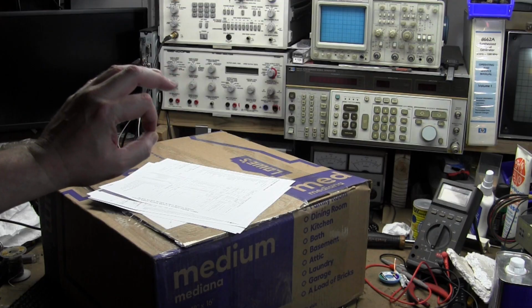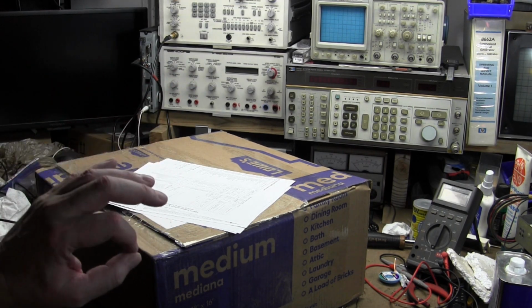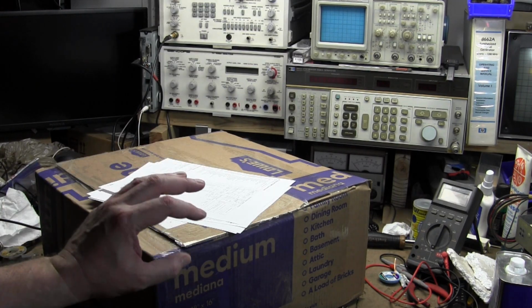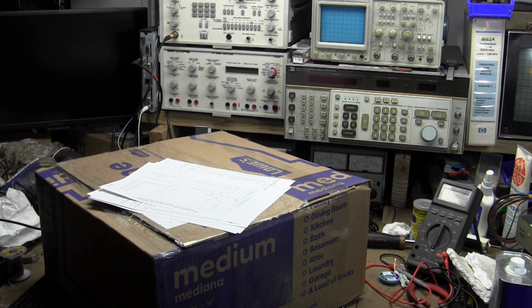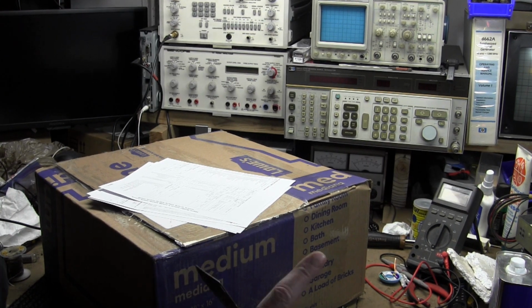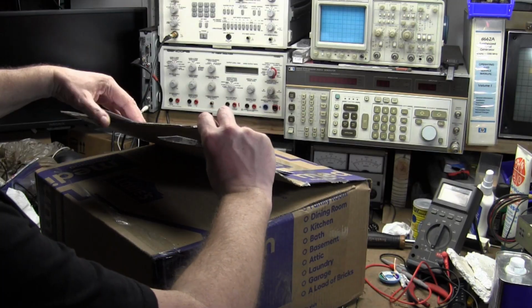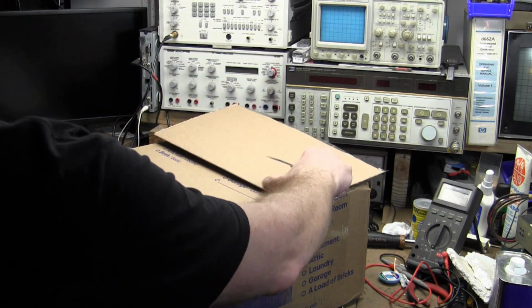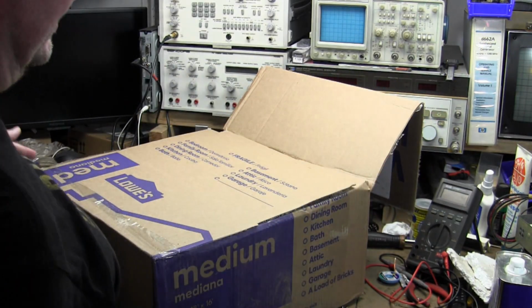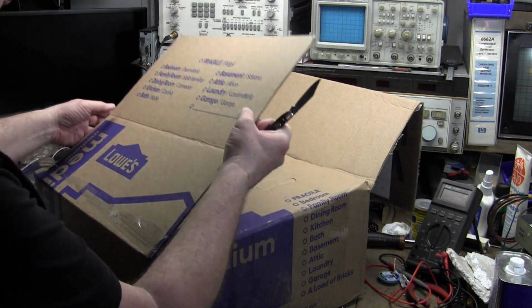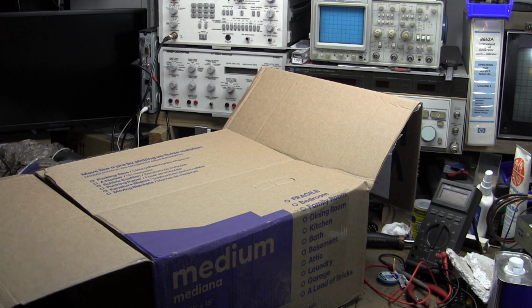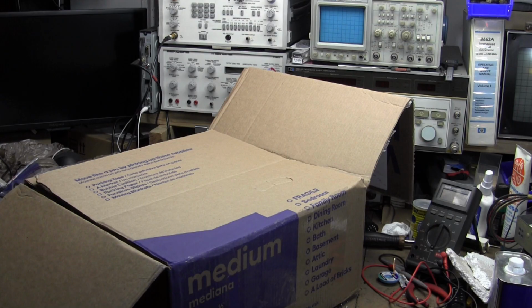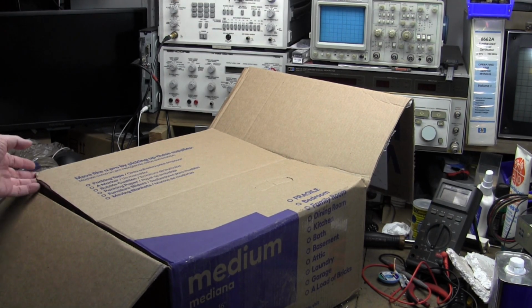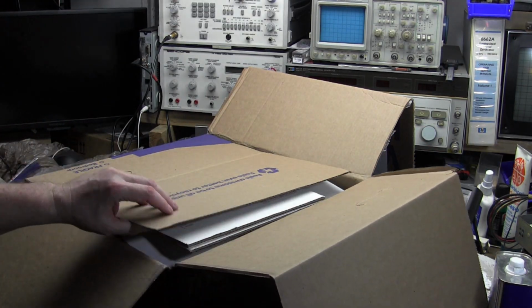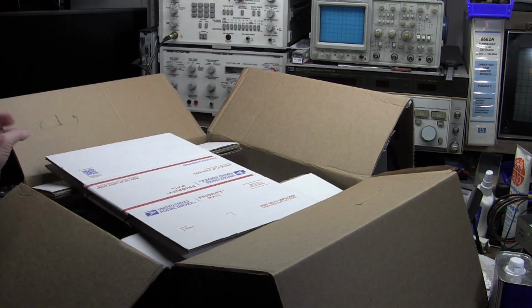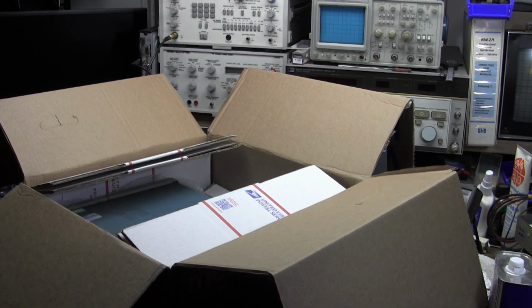And at least some, if not all, of the calibration is also done digitally. They probably have digital to analog converters that output offset voltages to compensate or adjust biases on things, and gain and whatnot. Losing that is really bad because then it's out of calibration, and unless you just want to look at a crude waveform and not take exact readings, you need it calibrated. If you lose that, you've got to recalibrate it yourself, and unless you're a metrologist with really nice voltage sources and meters that are accurate, you can't fully recertify it - most people aren't capable of it, including myself, because I don't have any of that.